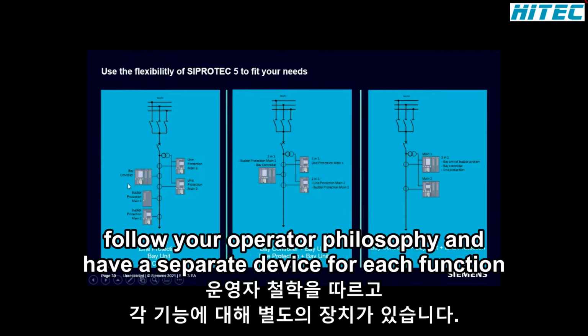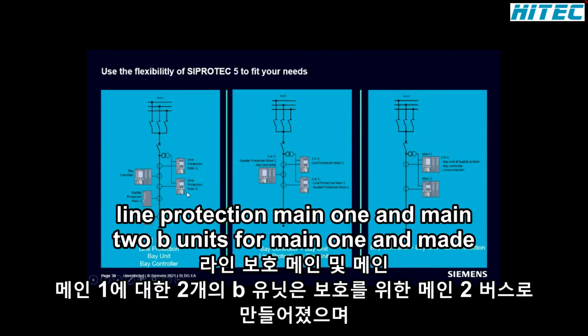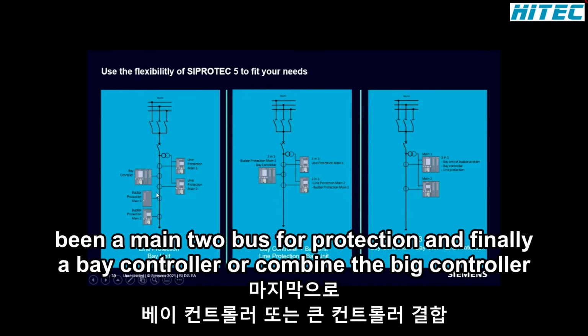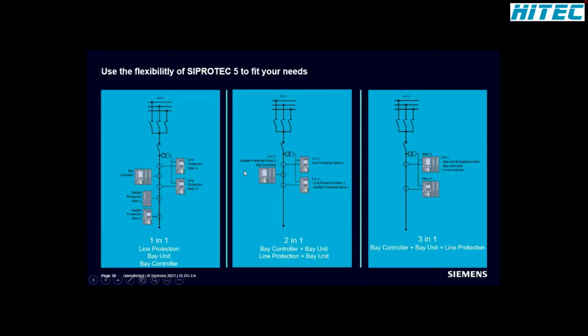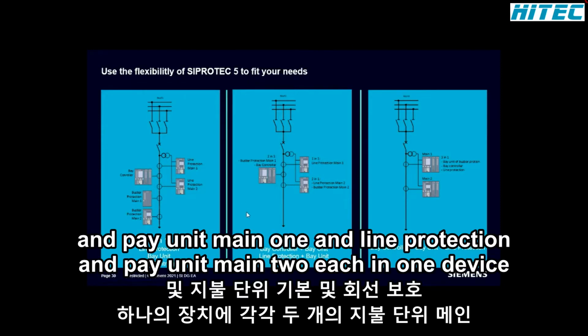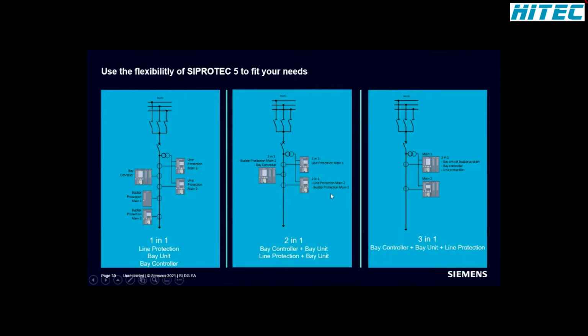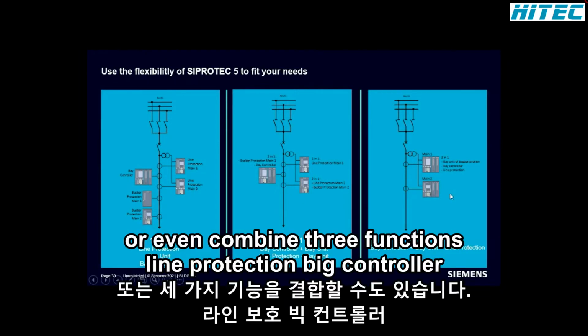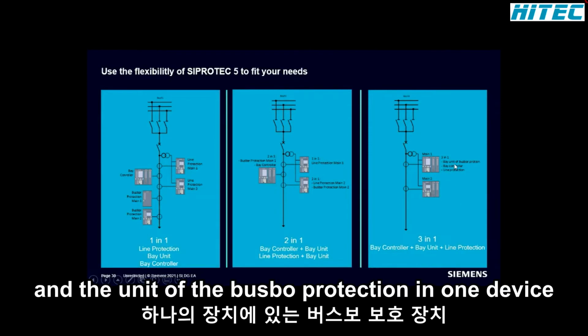Follow your operator philosophy and have a separate device for each function: line protection, main 1 and main 2, bay units for main 1 and main 2 busbar protection, and finally, a bay controller. Or combine the bay controller and bay unit main 1 and line protection and bay unit main 2 each in one device. Or even combine 3 functions: line protection, bay controller, and bay unit of the busbar protection in one device.